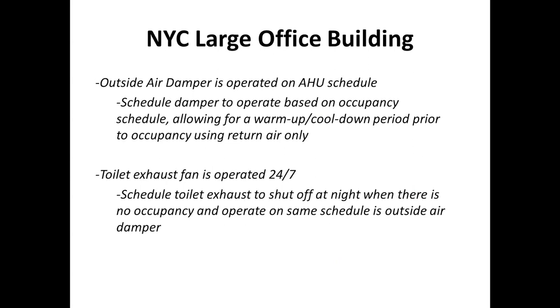When there's no occupancy in the building, ASHRAE 62.1 allows us to adjust outside air and actually shut it off or go down to a minimum. So this damper didn't need to be operated until the first person enters the building. Knowing that this building enforces a strict schedule, we could schedule that outside air damper to operate based on occupancy while keeping the air handler turning on and off for the pre-warm-up and pre-cool-down period. This is much more efficient because you're no longer bringing in outside air that needs to be heated or cooled. There is still an economizer override, so if it was efficient and cost-effective to bring in cooler air versus using the cooling coil, the unit still would, but generally the outside air damper is kept closed until the periods of occupancy.